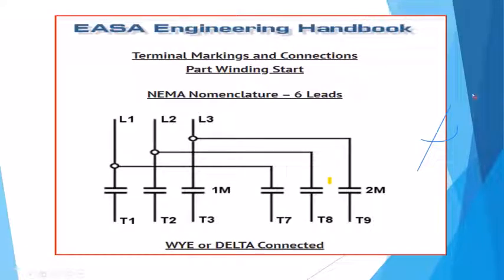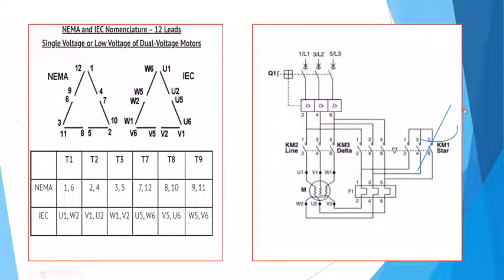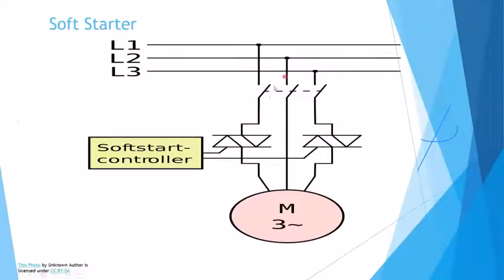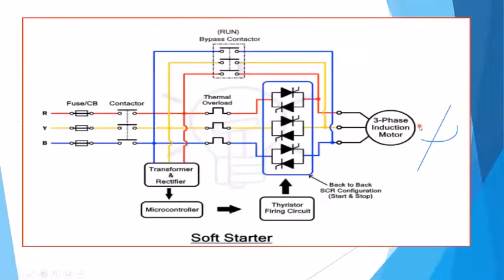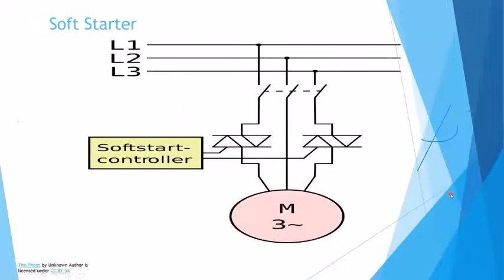That's the ultimate way. The next way, which a lot of the power companies want today, is the soft starting, and this is the diagram here, which is basically thyristors. Those are basically SCRs that are on only while you're starting the motor and shutting it off on a normal basis. This is, I feel, the best alternative to a VFD if you have the proper pump curve and you have it all designed.